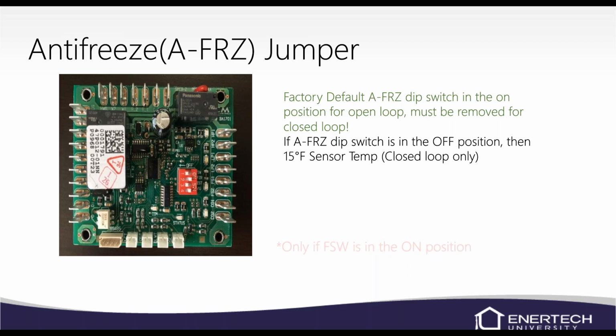A lot of times we see this fault on a new install in the winter where the installer forgets to switch that over and they have antifreeze in the system and it gets below 30 degrees, it'll lock the unit out. It's not because it's frozen. The installer just forgot to look at the different temperature sensor ranges depending on the dip switch.